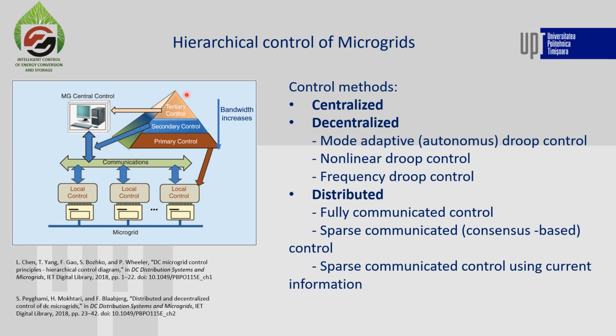The tertiary control takes responsibility of power management between the microgrid and upper grids, and it is also commonly referred to as the energy management system. Also, this tertiary control has to prepare dispatch schedules inside of the microgrid to achieve the optimum operation. Now, in more detail, the hierarchical control is implemented using mainly three types of controls: centralized, decentralized, and distributed.